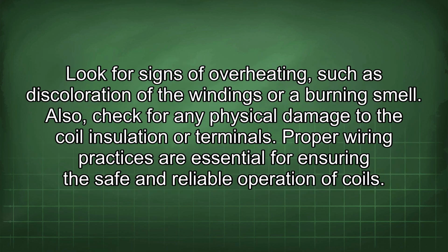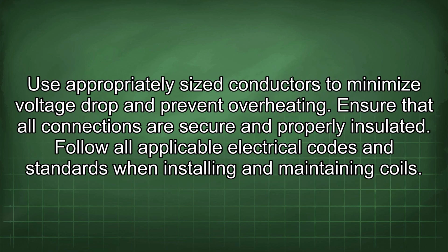Look for signs of overheating, such as discoloration of the windings or a burning smell. Also, check for any physical damage to the coil insulation or terminals. Proper wiring practices are essential for ensuring the safe and reliable operation of coils. Use appropriately sized conductors to minimize voltage drop and prevent overheating.